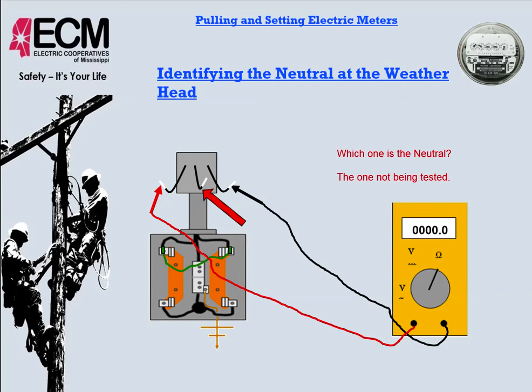Another way to do that is that you can go up the ladder and strip out all 3 and touch 2 of them together and use your voltmeter or your multimeter to ohm out down here at the bottom. But either way, we have to connect 2 of them and find the 2 that have 0 ohms of resistance between them. If it's the 2 outside ones here on the outside of the meter base, then the odd one, the one that's left, would have to be our neutral, and then we would hook our bare wire from our triplex to that, and our 2 insulated ones to the other 2 that ohm together. Then we would know that we got our line side voltages where they should be and our neutral connected where it should be as well, okay?